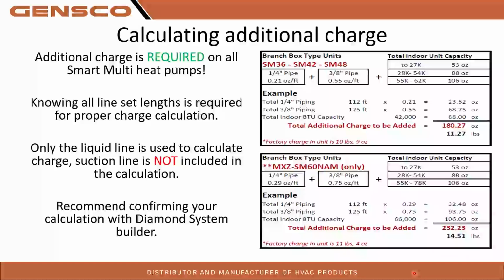So I highly, highly recommend Diamond System Builder, if you guys aren't using it, because if you build the system in Diamond System Builder or DSB and put all your pipe lengths in there, it will calculate the charge for you and tell you how much should be in that system, so you don't have to do the math. This is an exercise that we do in our 2-day M&P class. For any of you that have taken that, I have found that we have about a 70% failure rate when guys are calculating by hand. Usually in my class, I'll follow up that exercise with using Diamond System Builder to show them how much quicker and more accurate it is to run the system in DSB.